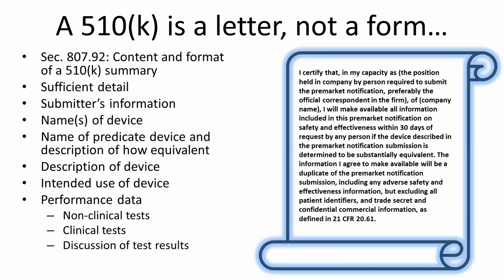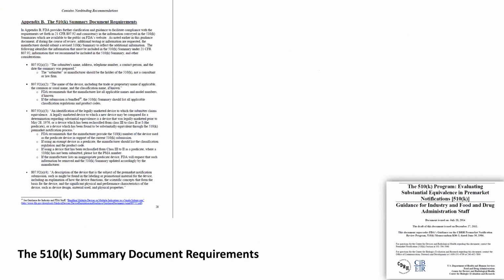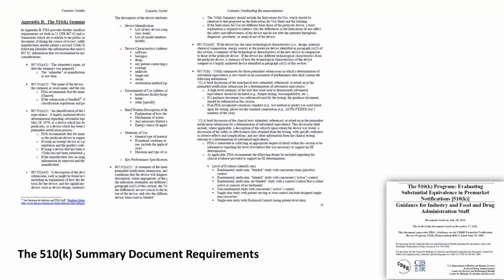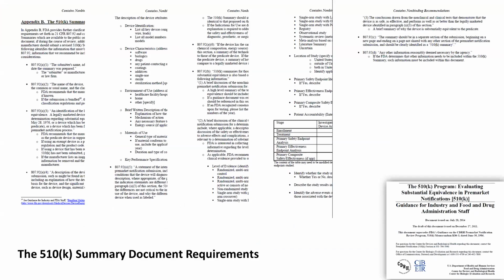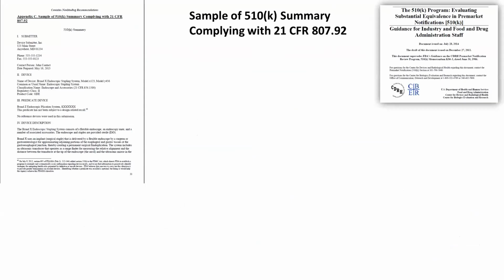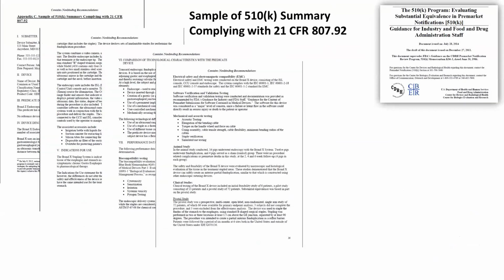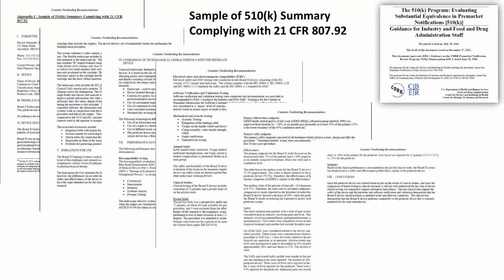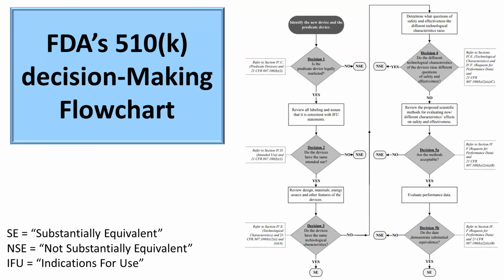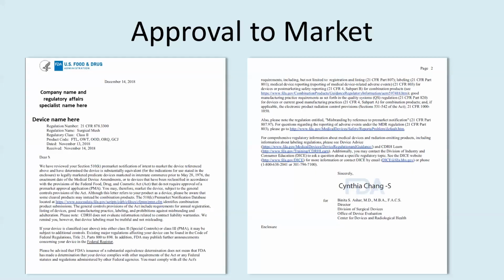It's not a form. It's very structured, just like an H&P. And you can see this is what the FDA offers as an outline for your 510K. And then again, a very short 510K example that they've made. Once you submit your 510K, then the FDA is going to go down this decision-making flowchart that they publish until they determine whether you have proven substantial equivalence, and you will get approval in the form of your letter that says you may go to market.